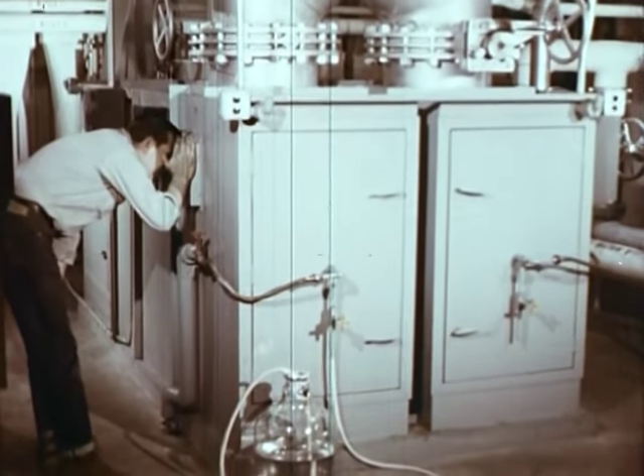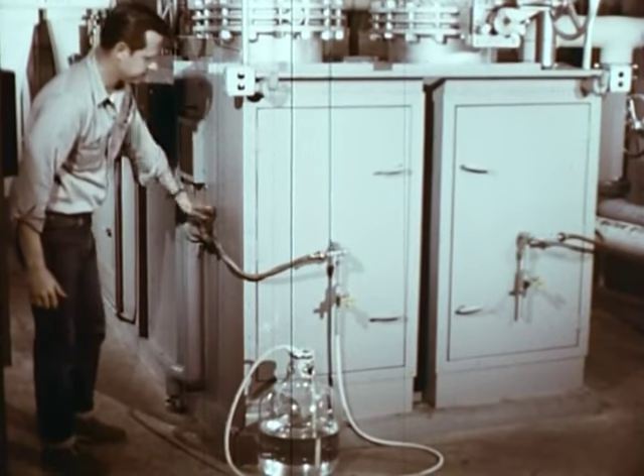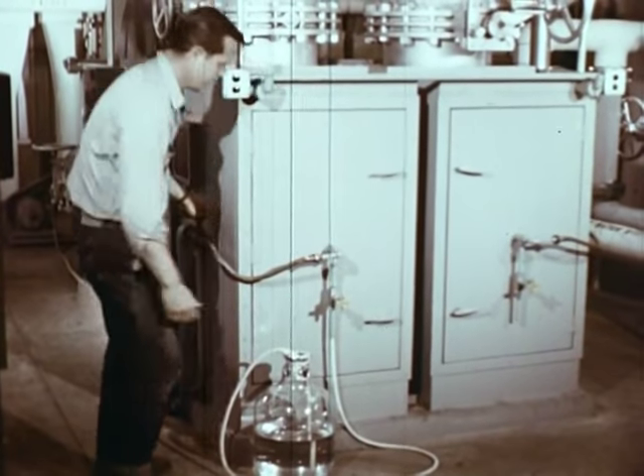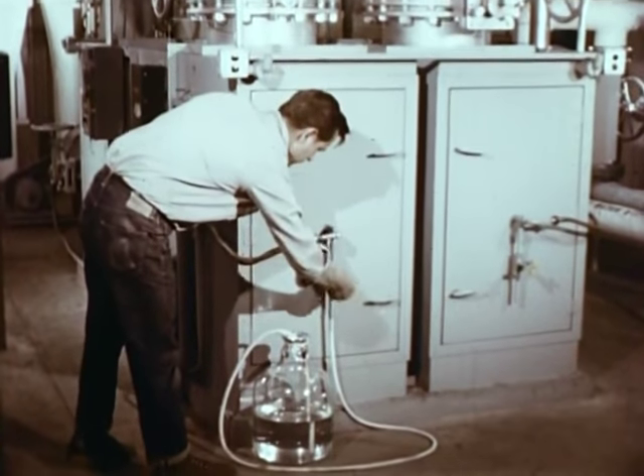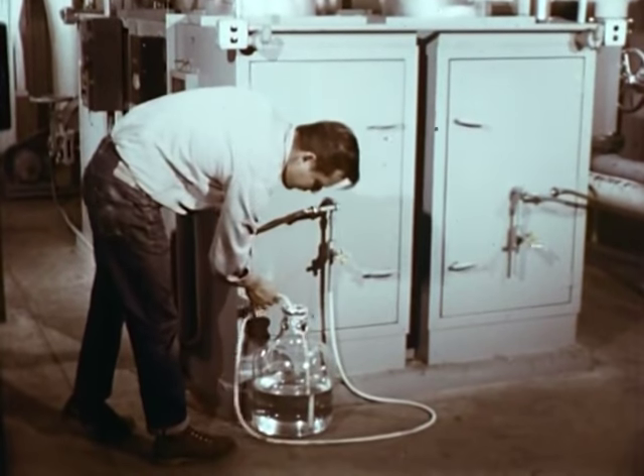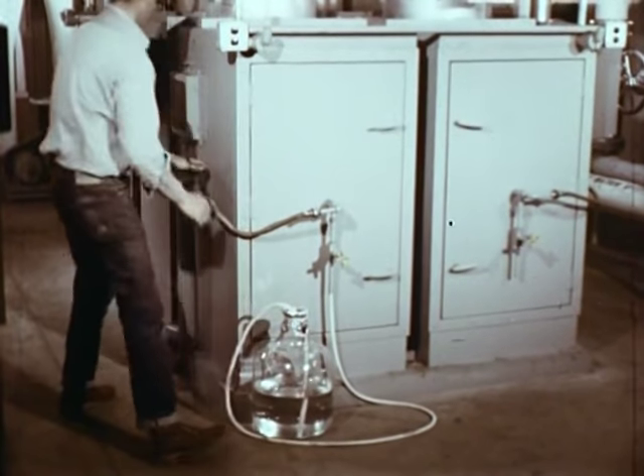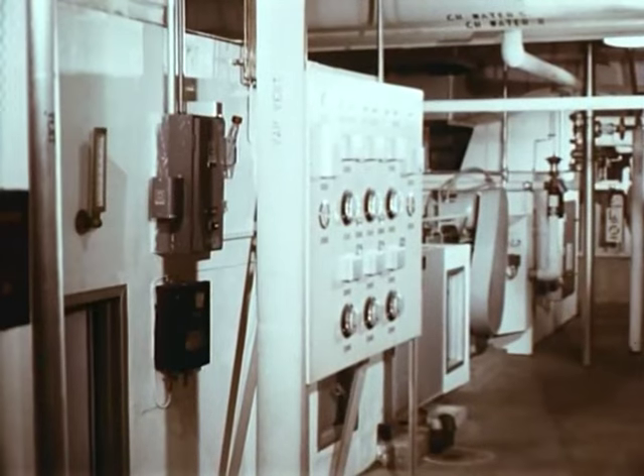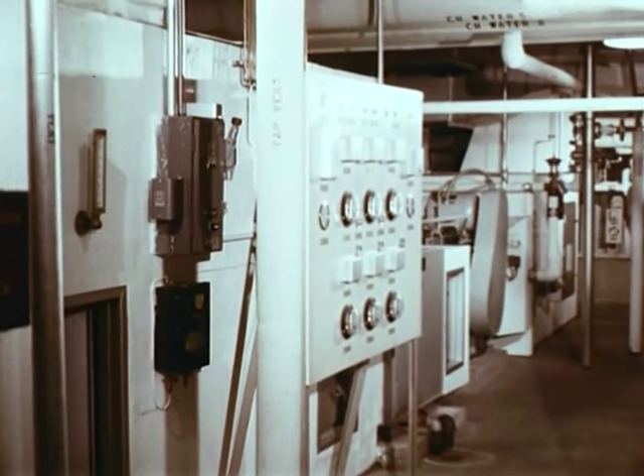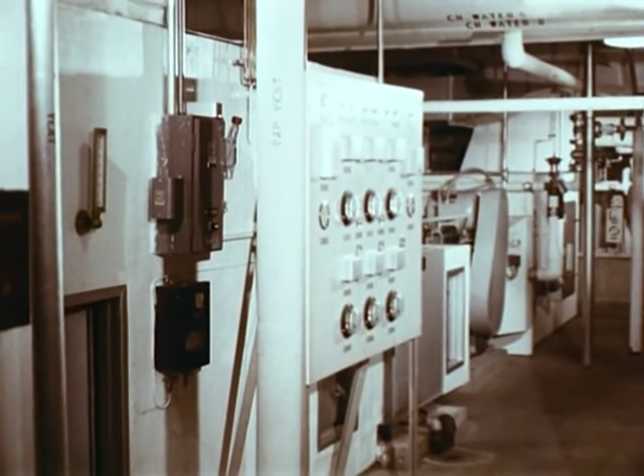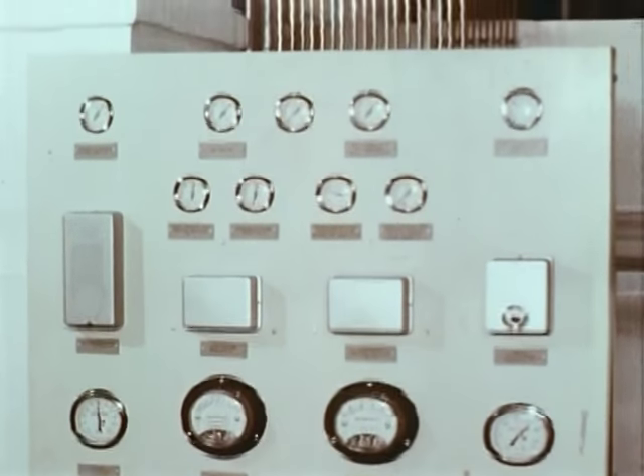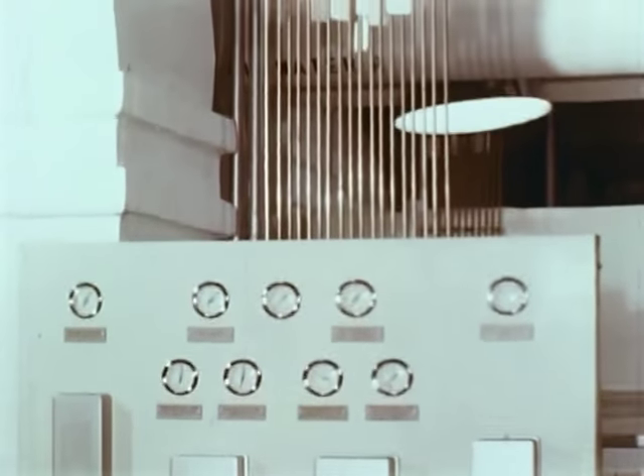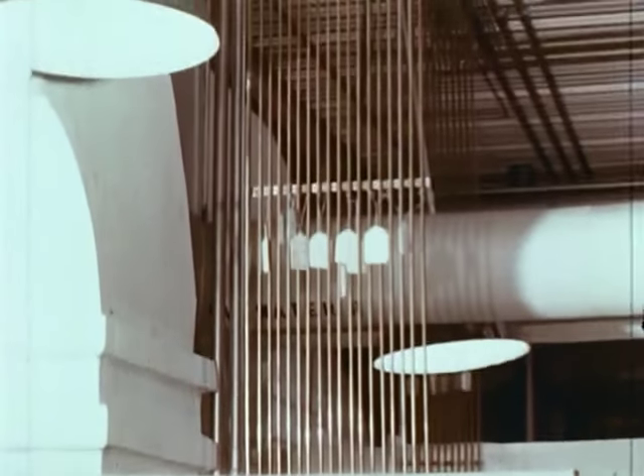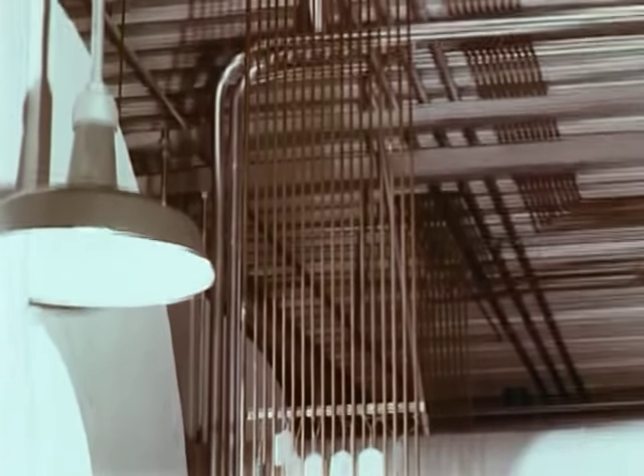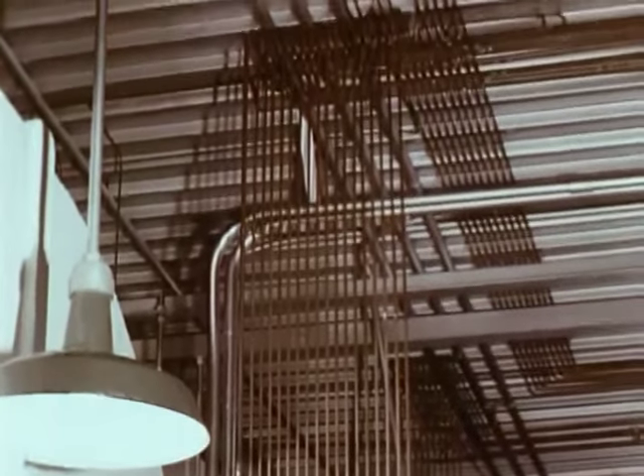Since the filters in a plenum must be changed periodically, provisions must be made for decontaminating both the filters and the plenum itself before opening the unit. A mixture of steam and formaldehyde is used as the decontaminating material. The facility's ventilation system should provide an interlock between the exhaust and supply blowers. This is to prevent pressurization of the infectious zones in case the exhaust blower fails. A pneumatic control system senses the air pressure in each room and assures correct air balance throughout the laboratory.